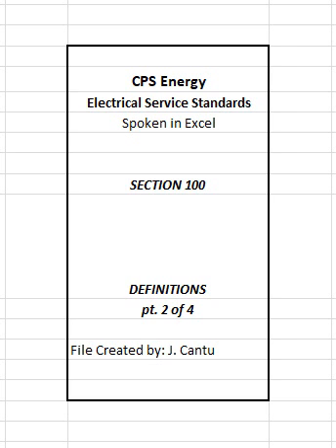Total harmonic distortion is an expression of the total harmonic content of a voltage waveform. The harmonic distortion, or harmonic content, of a waveform is usually expressed as the square root of the sum of the squares of each of the harmonic amplitudes, with amplitudes as a percent of the fundamental voltage amplitude. High-rise building. A residential use building consisting of 6 or more floors.